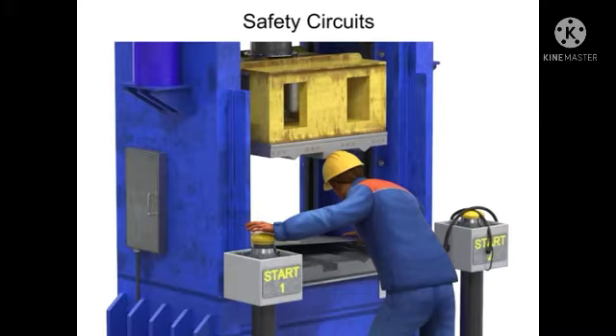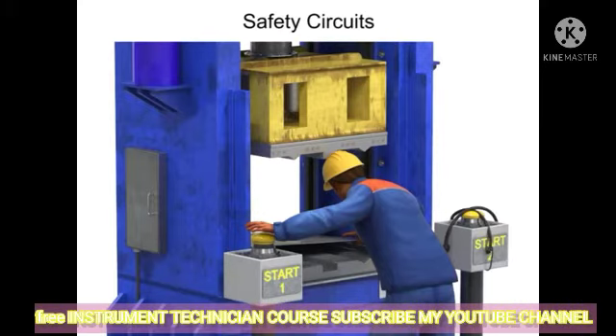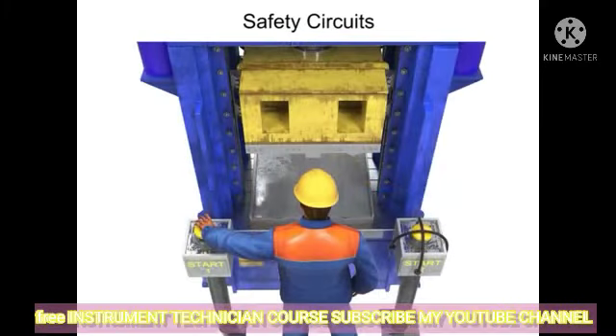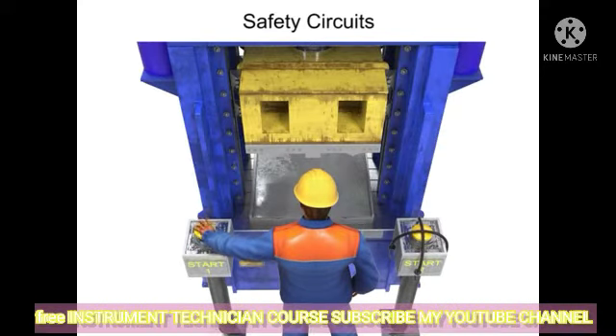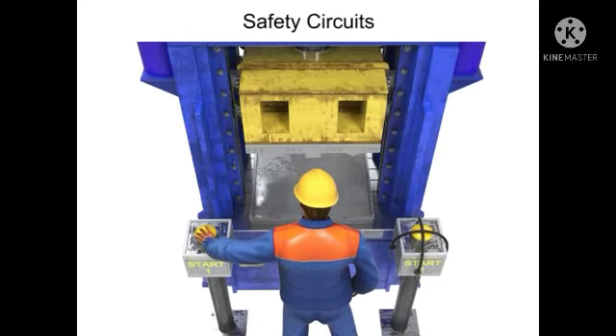To prevent this unsafe condition but still permit a single operator, anti-tiedown circuits are employed. An anti-tiedown circuit requires that the operator actuate both individual controls at the same time. If either control is prematurely actuated or continuously tied down, the cycle will not operate.